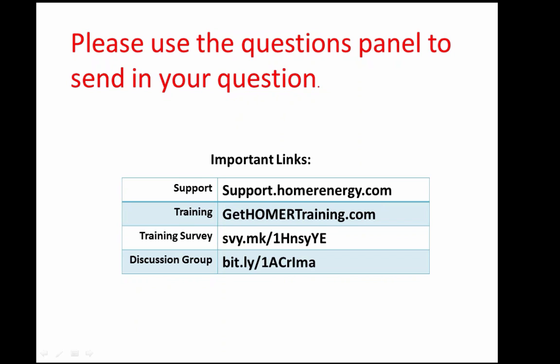Can I define priorities? Yeah. Homer by default uses an economic dispatch, and the way it does that is it looks at, well, what's the cheapest way for me to meet my load at a particular time step? It doesn't look ahead, but it does make the cheapest decision within that time step, and we've got two permutations on that because when you have storage integrated into it, it's actually a relatively involved decision.